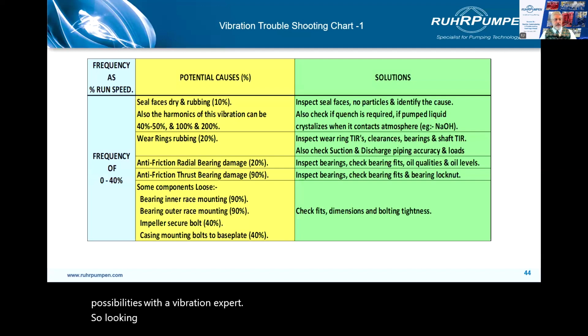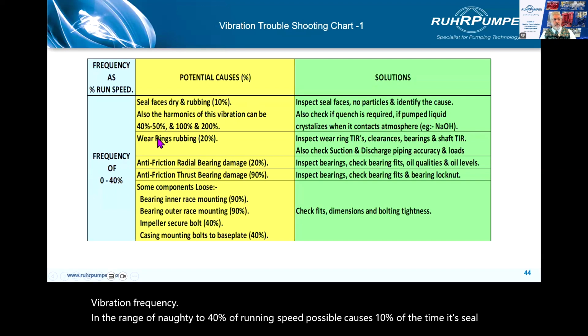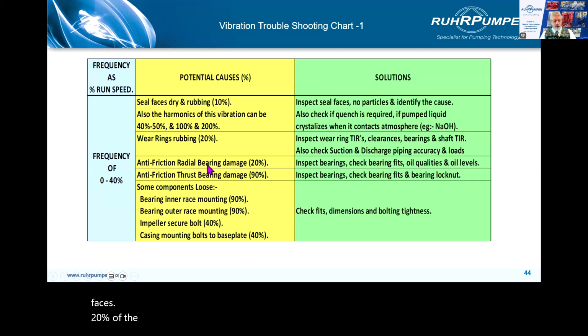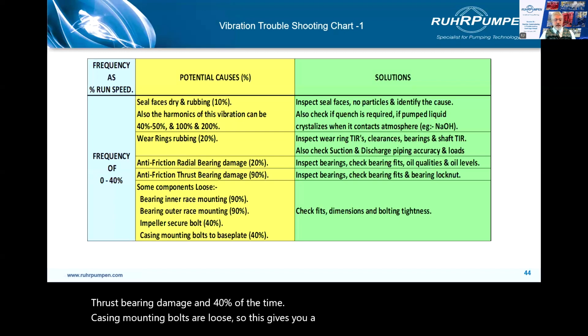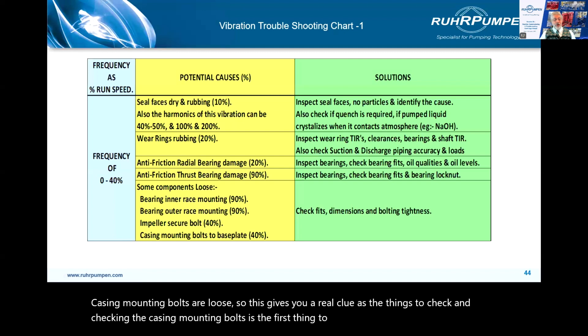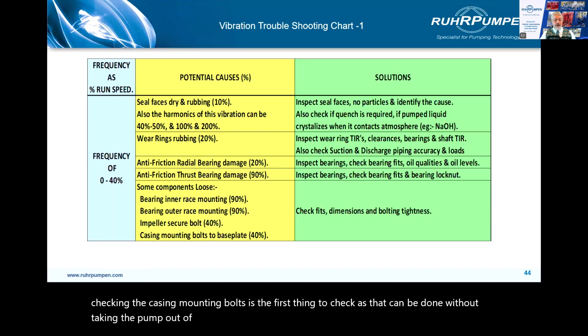So looking at this first slide, vibration frequency in the range of 0 to 40% of running speed. Possible causes, 10% of the time, it's seal faces. 20% of the time, radial bearing damage. 90% of the time, thrust bearing damage. And 40% of the time, casing mounting bolts are loose. So this gives you a real clue as to things to check. And checking the casing mounting bolts is the first thing to check, as that can be done without taking the pump out of service and returning it to the workshop.